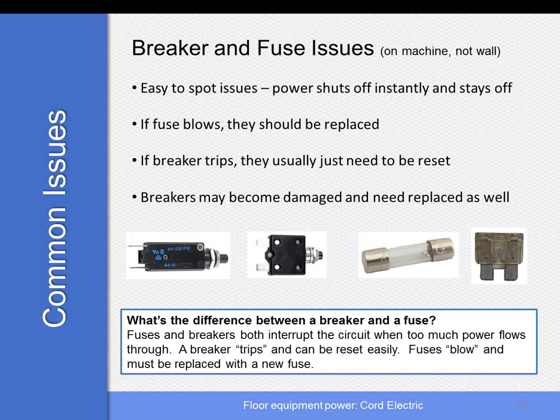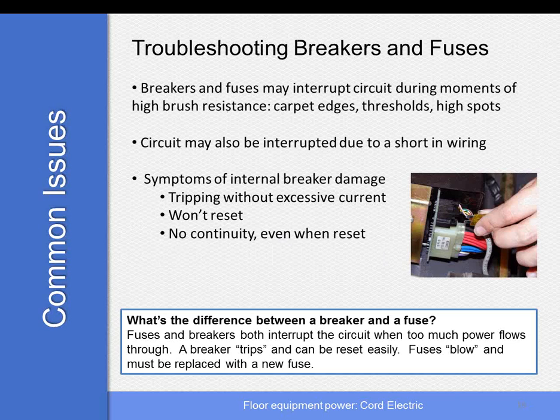It may overheat beyond what its thermal capability is, and you could run into a breaker where you won't be able to reset the circuit breaker, or if you are able to reset it, you still have no continuity, or you'll have a breaker that trips even when there's not an excess of current applied.